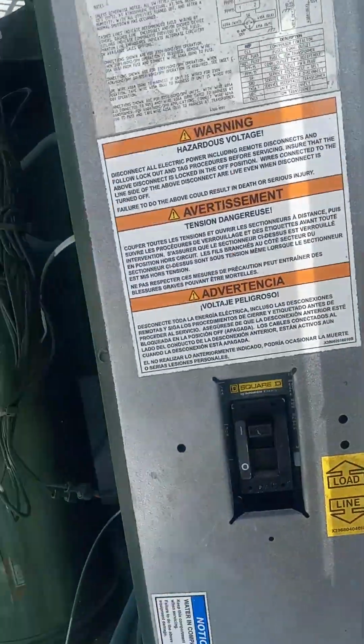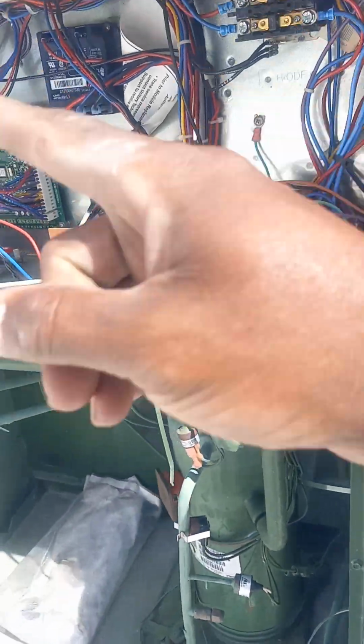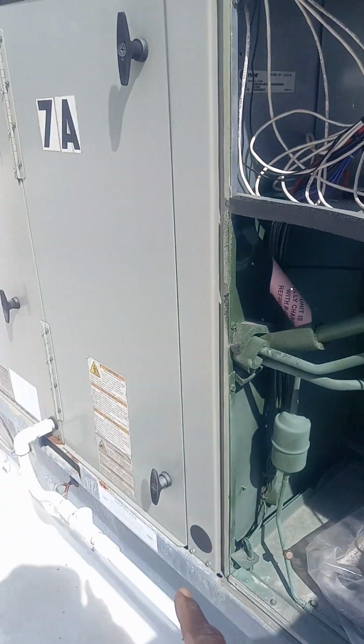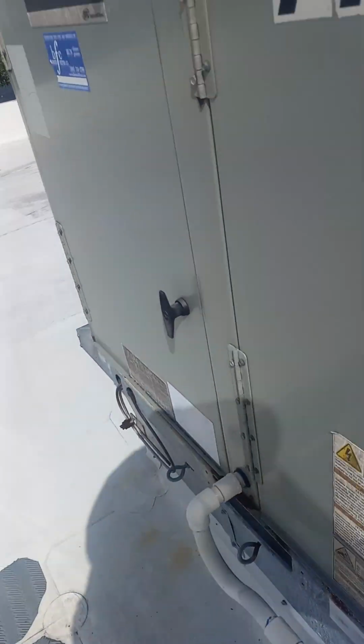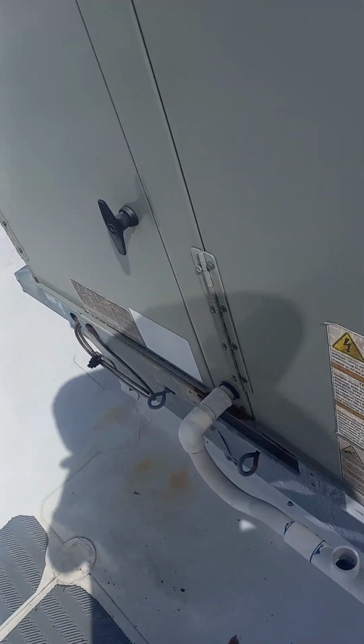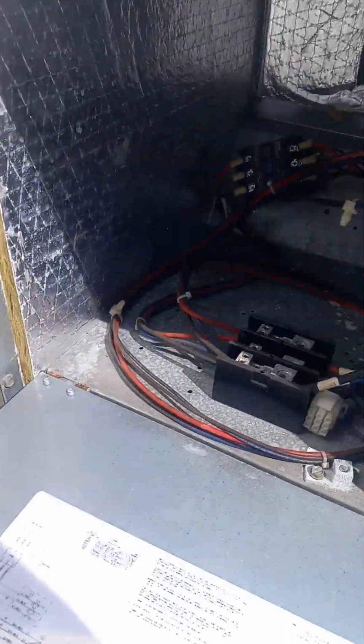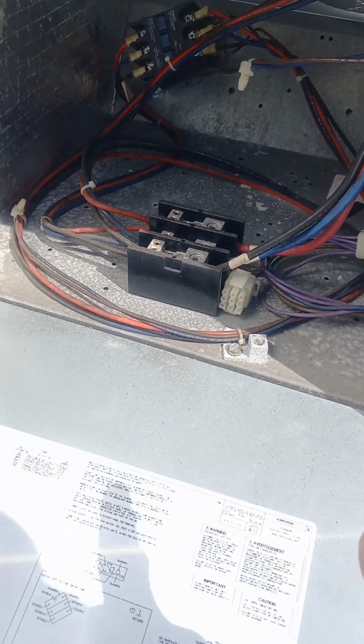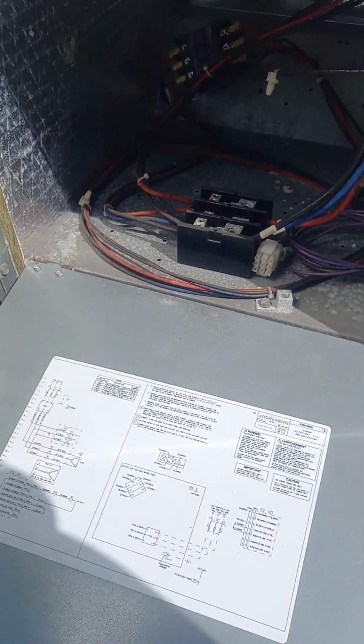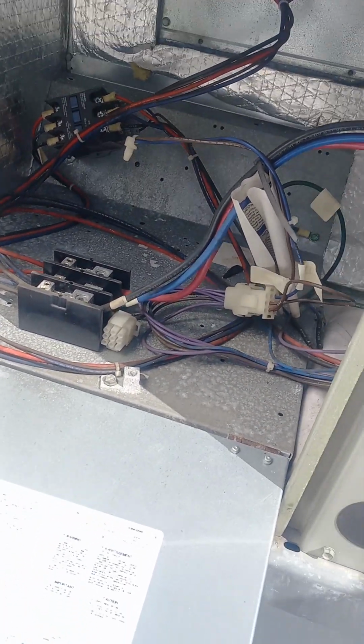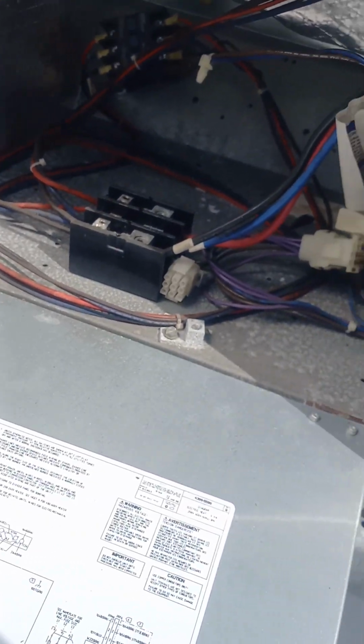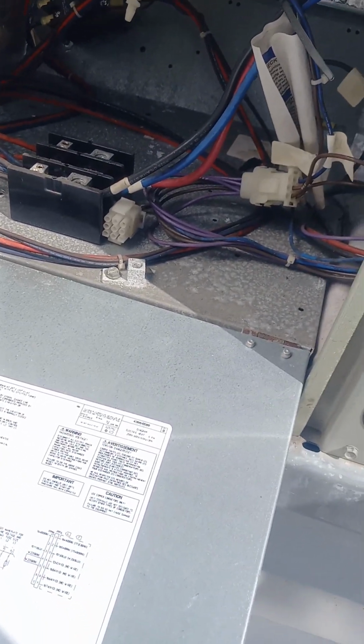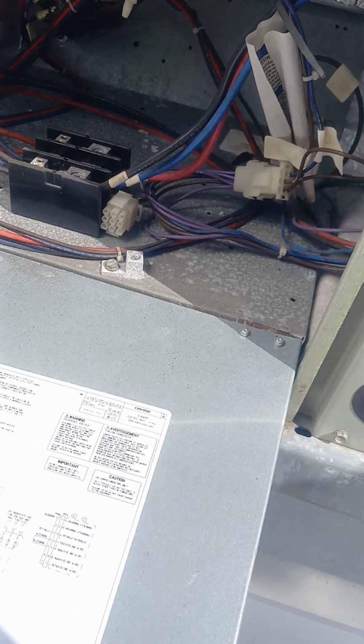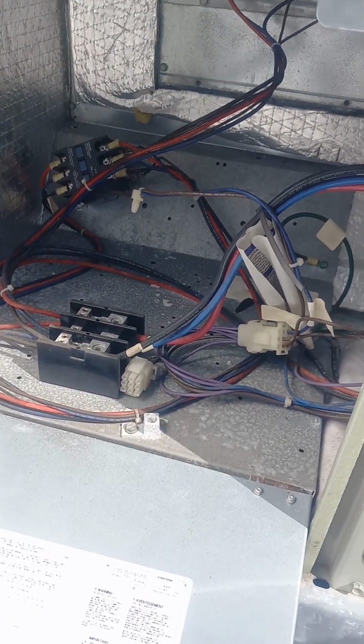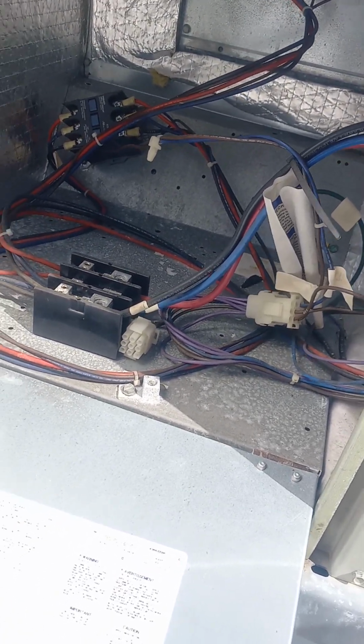Power coming in from there, it goes over into the heater section. So this is the heater section right here. Open up here. Low heater section. That's high voltage. That's 460 volts, so you don't want to touch that. And right now the unit is live. So sometimes when you're doing the testing or maintenance, you have to check the unit for amperage and all that stuff to make sure it's not over-amping and causing any issues.